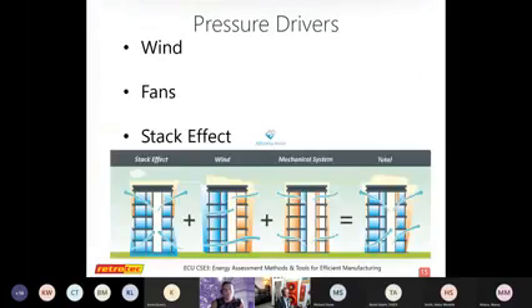So we have 3 pressure drivers that cause a leak in a building. The 2 most common ones are wind. Yep, the wind's blowing. And if we have holes in our building, then we can get outside air moving in. Fans, our mechanical systems, they induce pressures on the building, ventilation, things like that. So as we have air come in, that air's got to go back out someplace, and it usually just goes back out, leaks in the building.